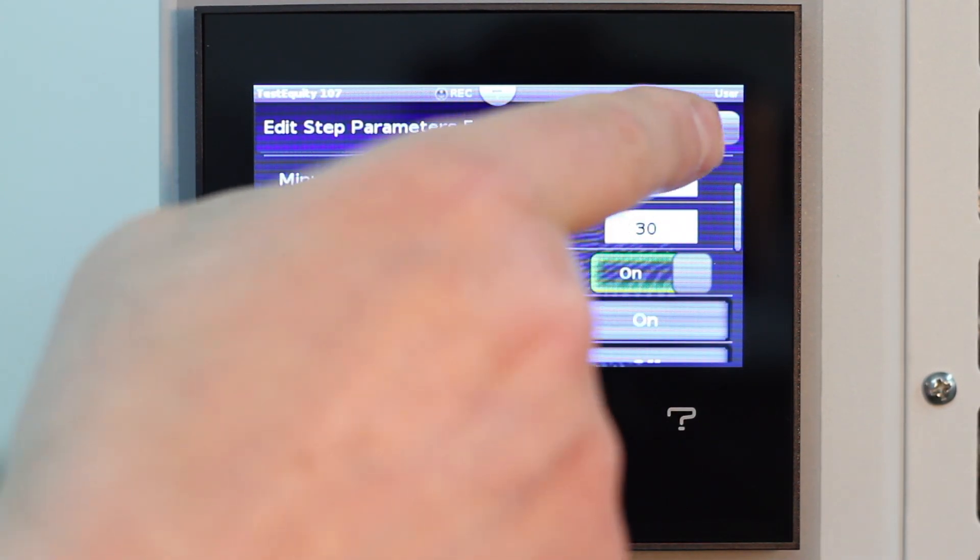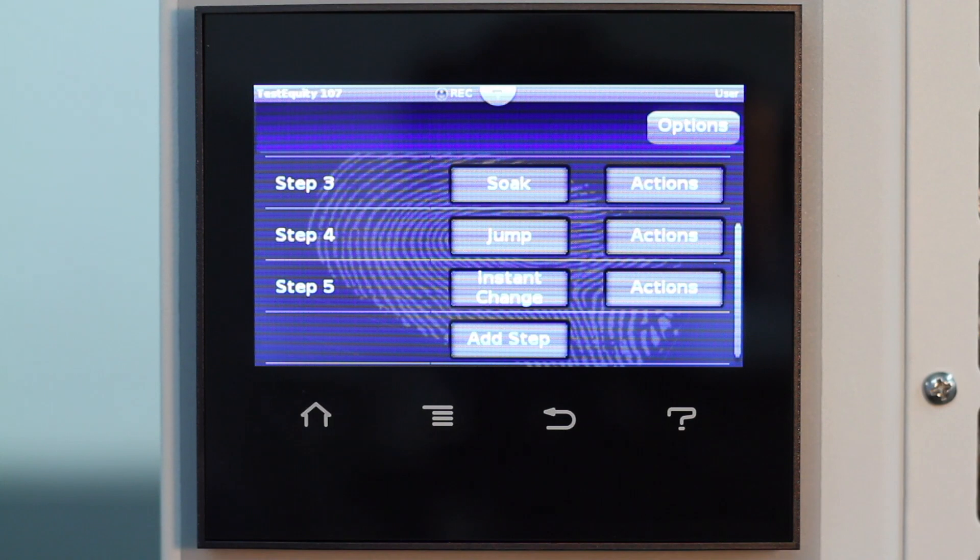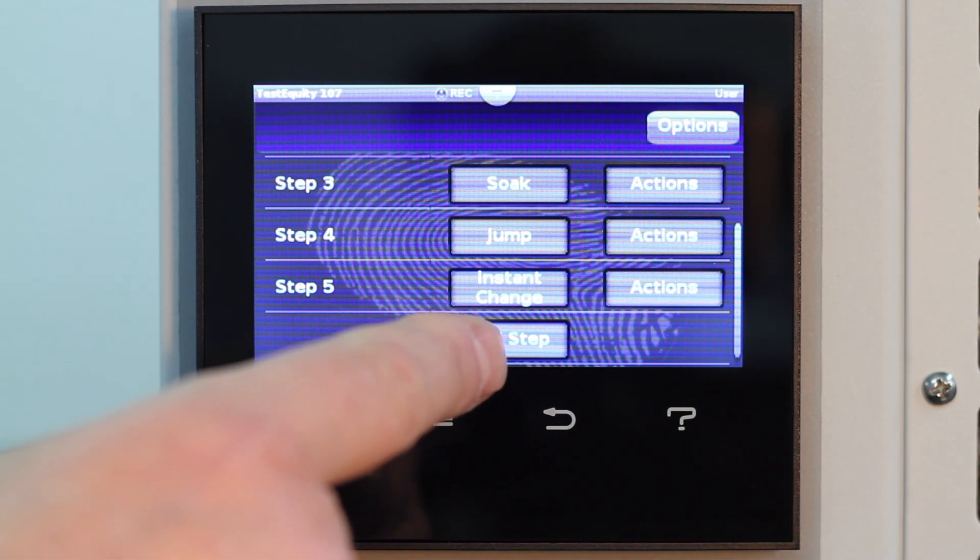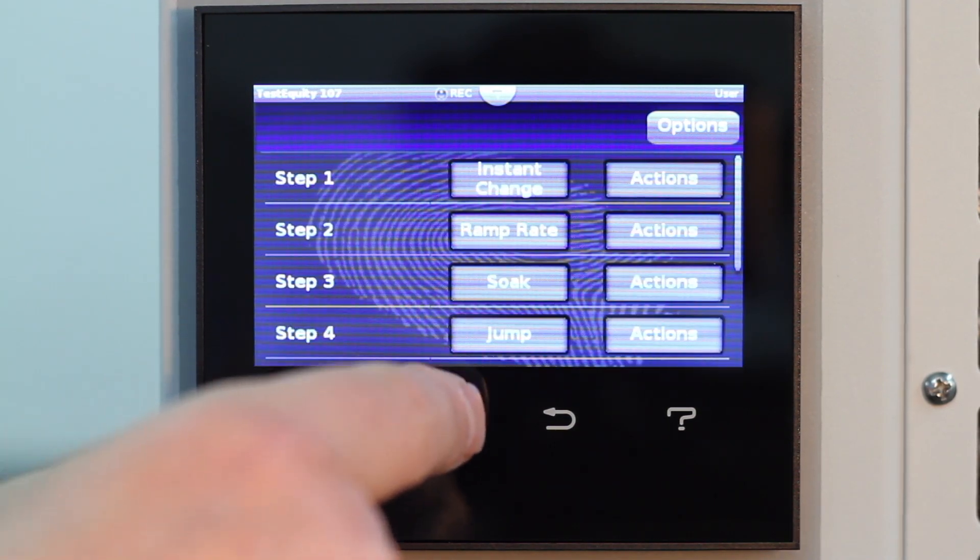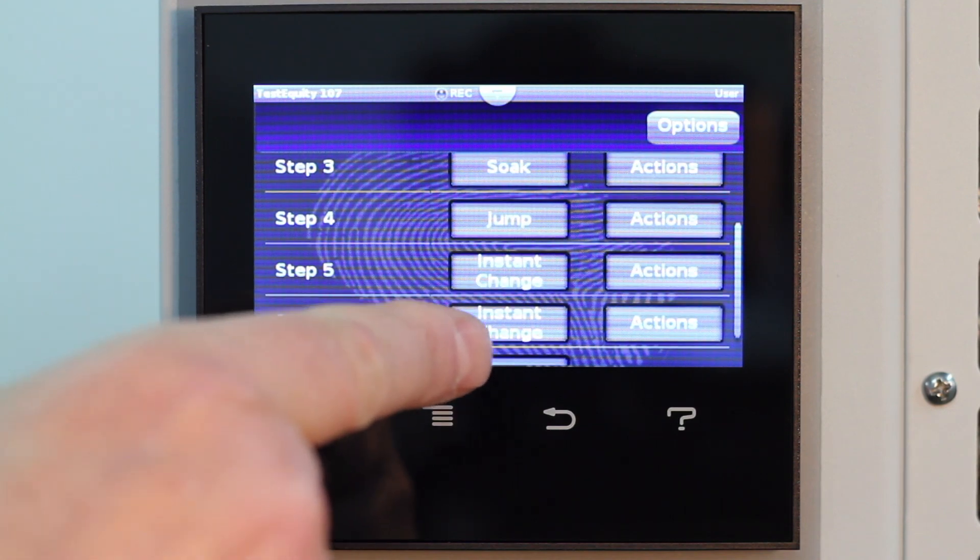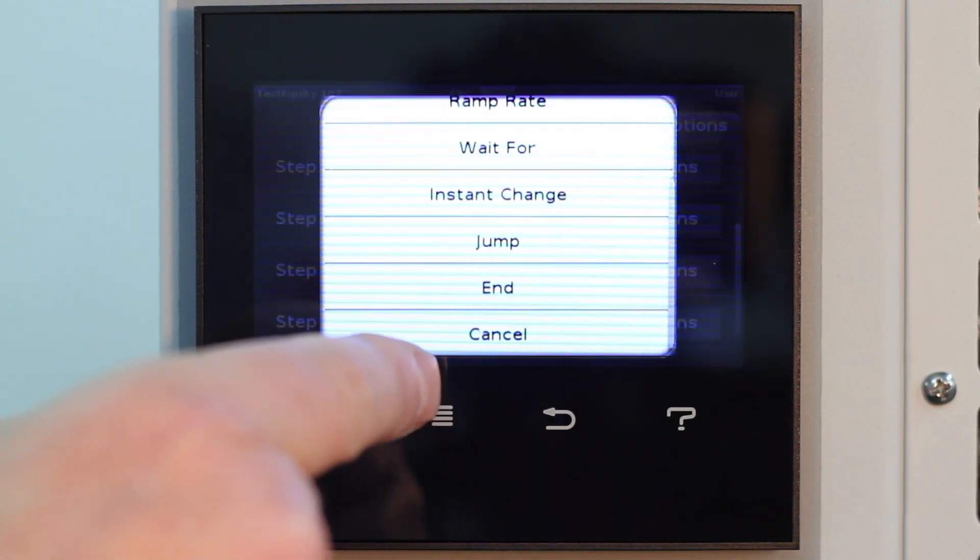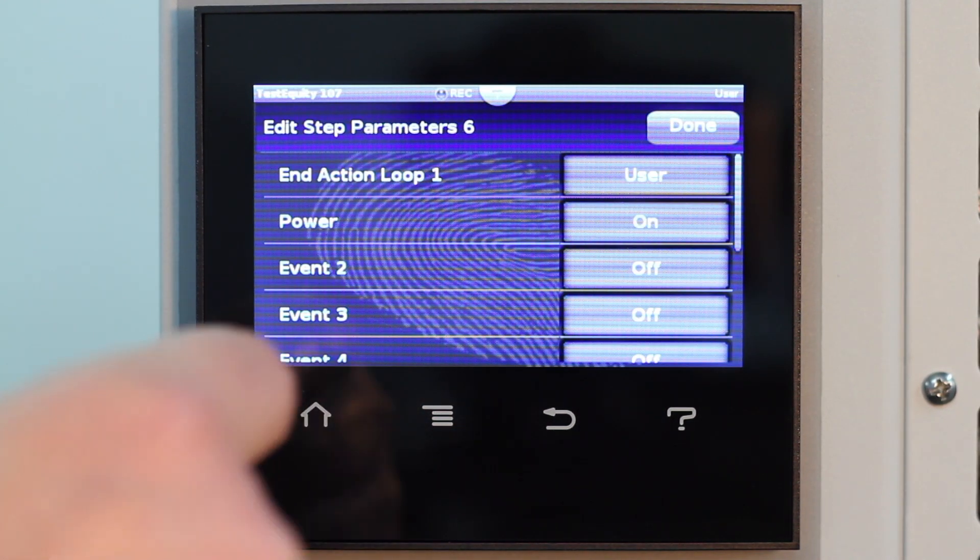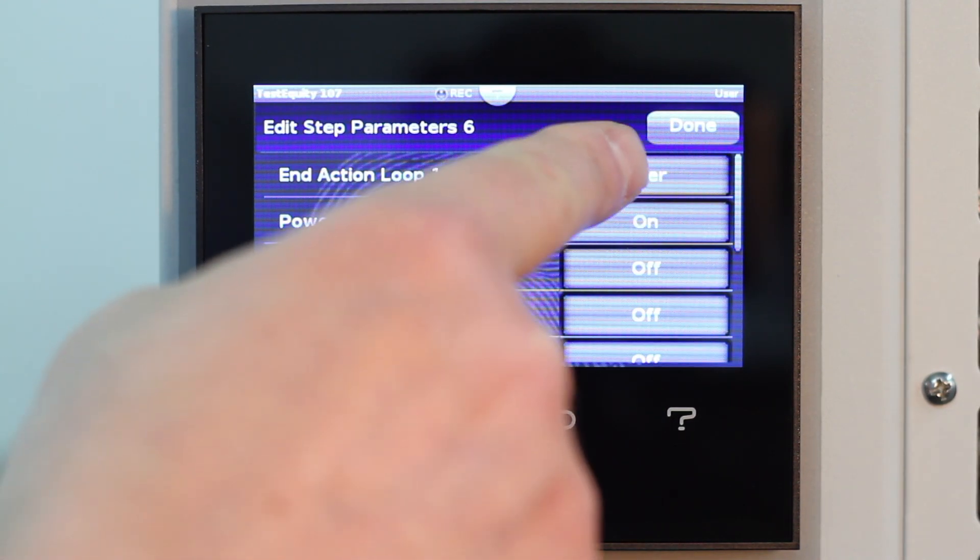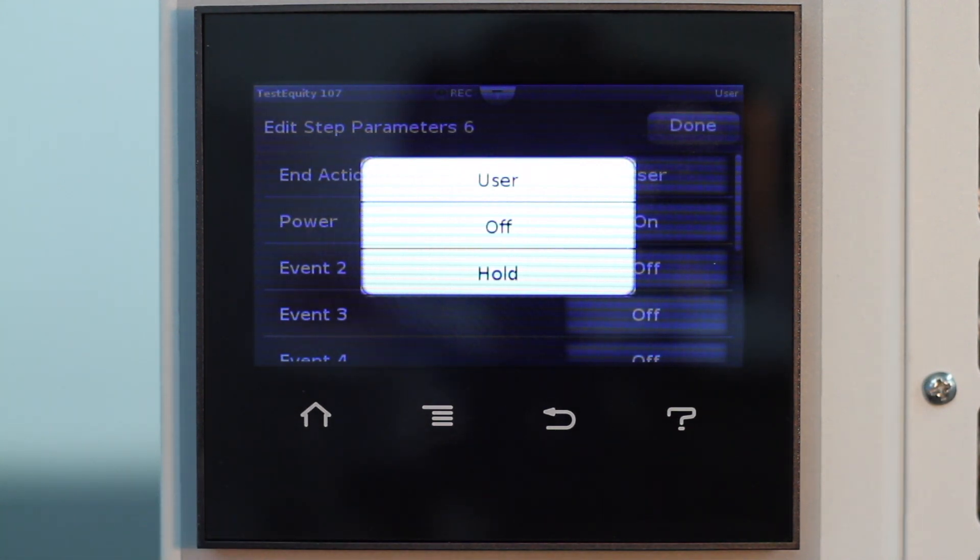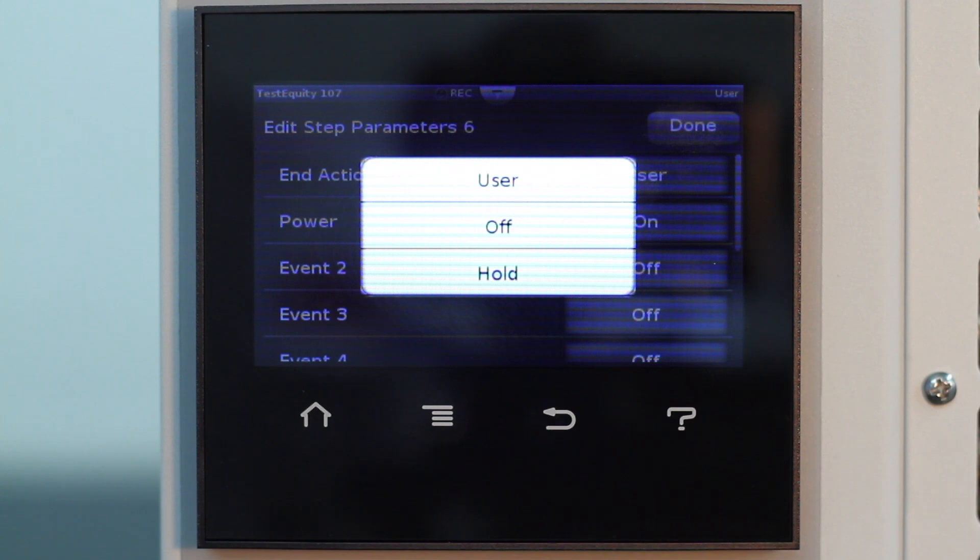Step 6. End the profile and turn the chamber off. The final Step 6 is an end step. You have three choices for end action. User will end the profile at the same manual settings you had before starting the profile. Off will turn the control loop off. This is not recommended for reasons that are discussed in the manual. Hold will end the profiles at the values in the next to last step. This is more desirable. The only difference is we will turn power off.